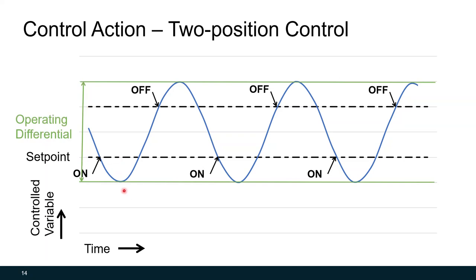The operating differential is what your space temperature truly fluctuates through during the control cycle. For example, if the set point is 70 and the control differential is 2, the operating differential might span from 69 to 73. If the control differential is too wide, the operating differential gets wider and occupants may not be comfortable. But if the control differential is too small, equipment turns on and off too frequently, leading to wear and potentially requiring early replacement.